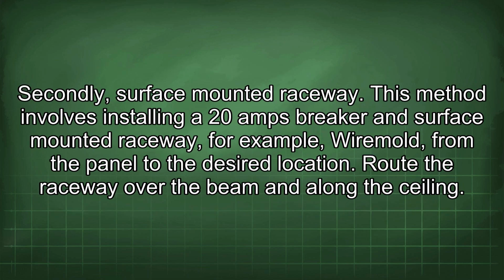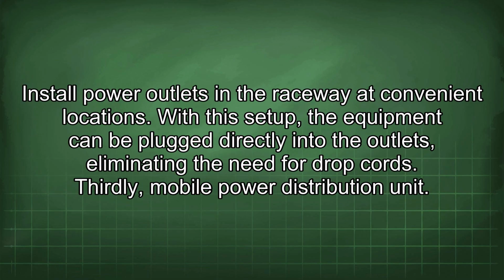Secondly, surface-mounted raceway. This method involves installing a 20 amps breaker and surface-mounted raceway, for example, Wiremold, from the panel to the desired location. Route the raceway over the beam and along the ceiling. Install power outlets in the raceway at convenient locations. With this setup, the equipment can be plugged directly into the outlets, eliminating the need for drop cords.